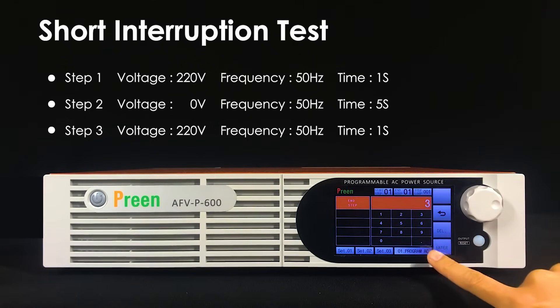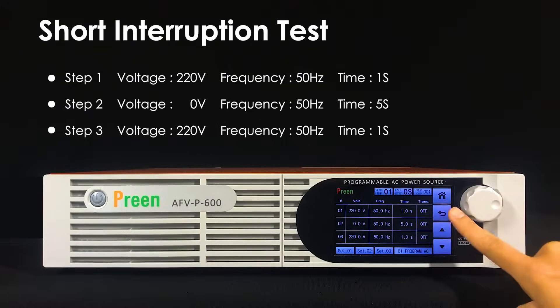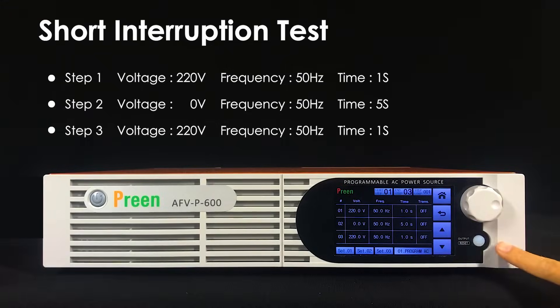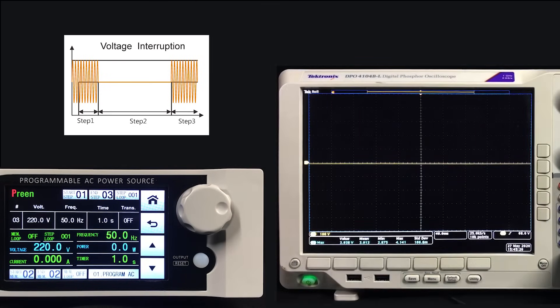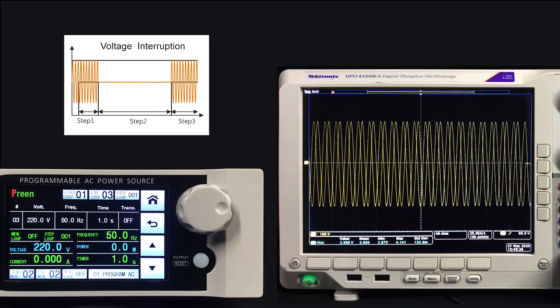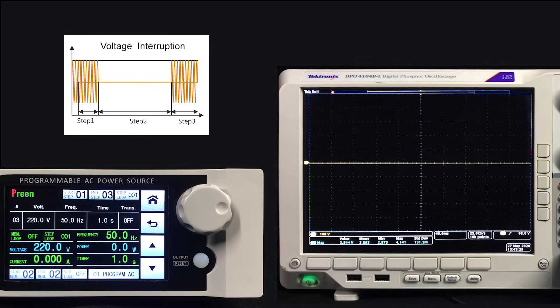Finally, press the output button to run. From the oscilloscope we can see that the voltage drops to 0 volts and returns to the nominal 220 volts after 5 seconds. This demonstrates how to use the AFV-P series to generate a voltage interruption.